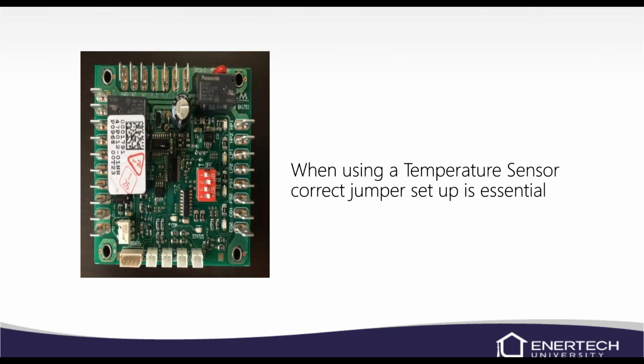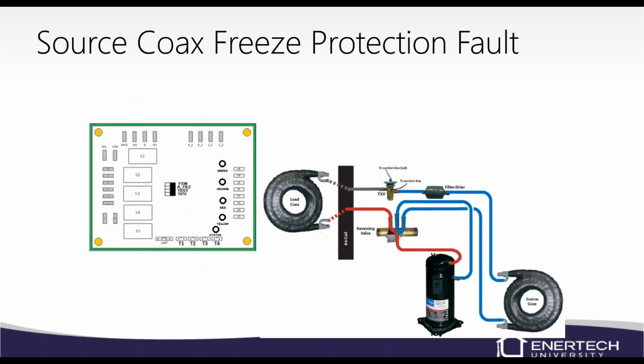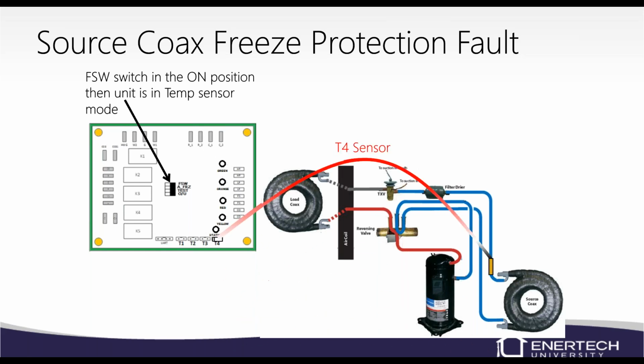So when using temperature sensors, it's important to have the proper dip switch settings, that red box right there in the middle. So again, if we're looking at a source coax freeze protection fault, the source coax is in the lower right-hand corner of this picture. If the flow switch, FSW switch, is in the on position, then we're monitoring a thermistor that's located on the source coax refrigerant line, not even the water line. It's looking at refrigerant temperature.